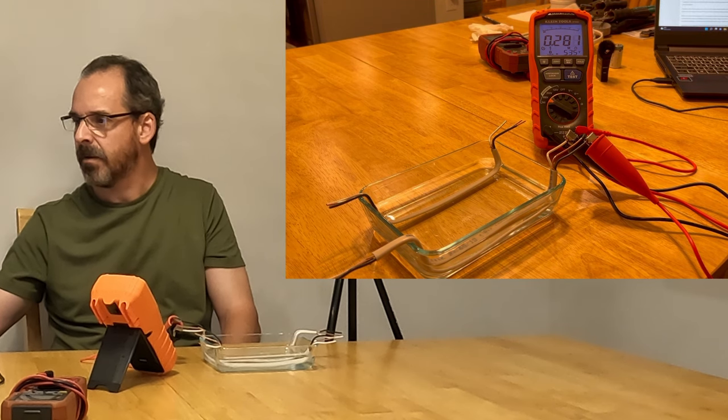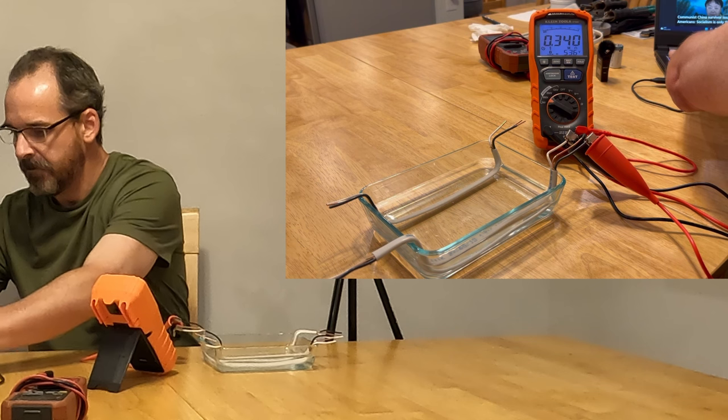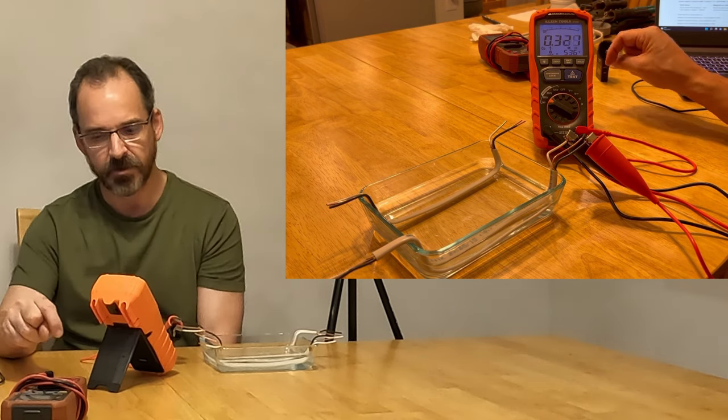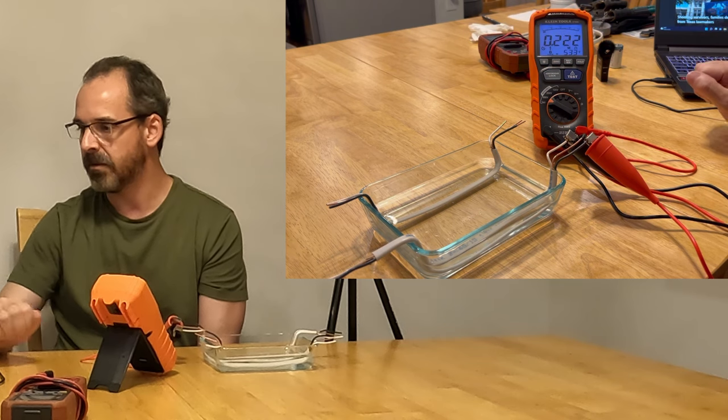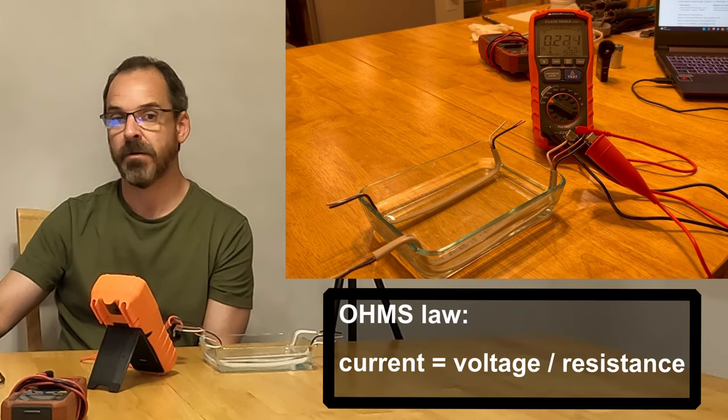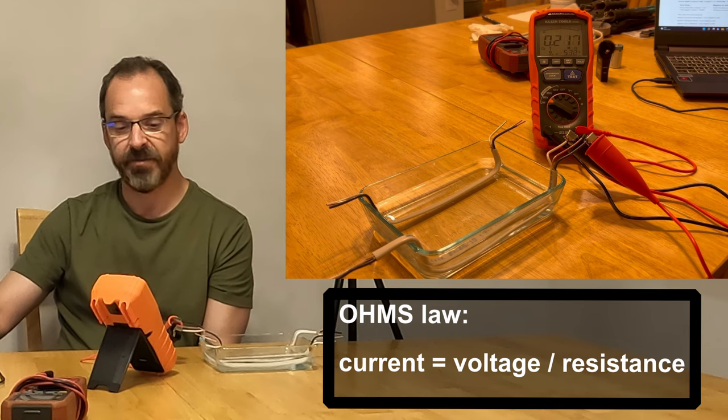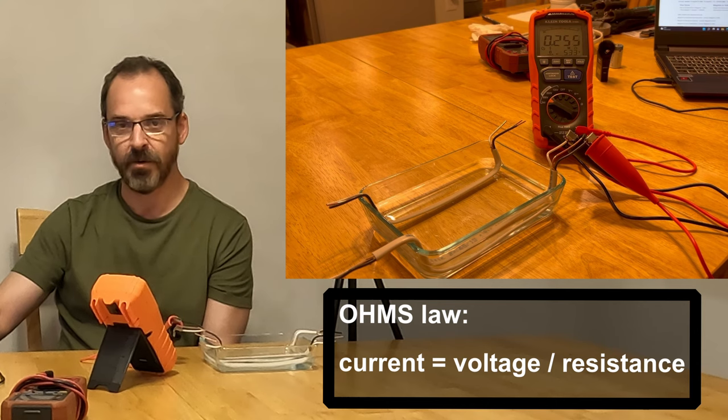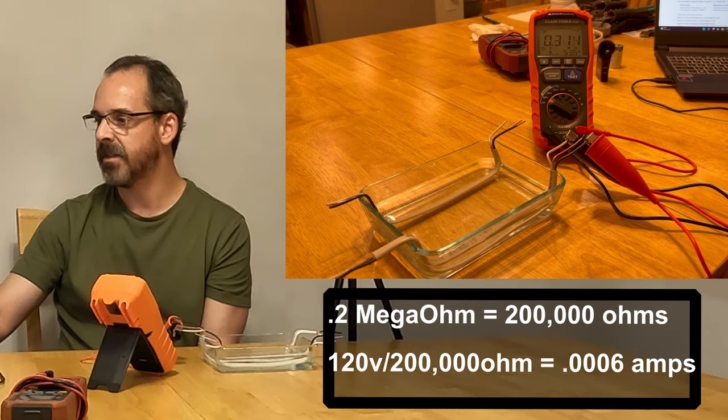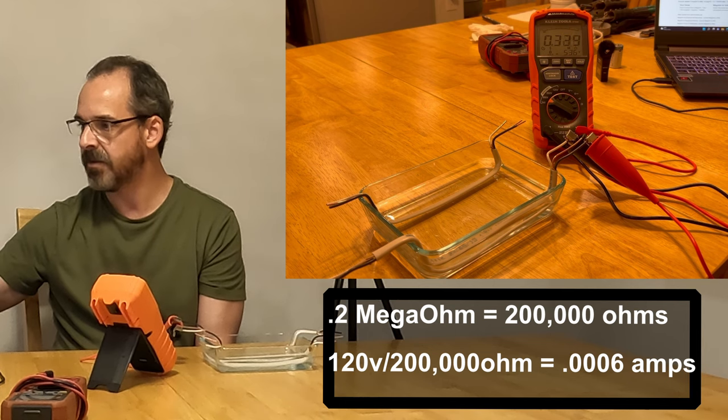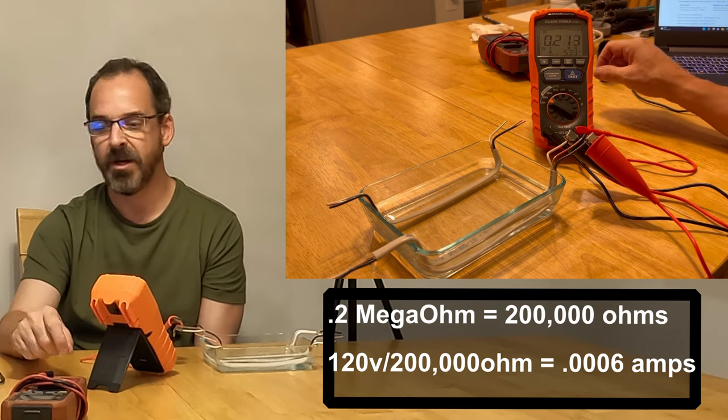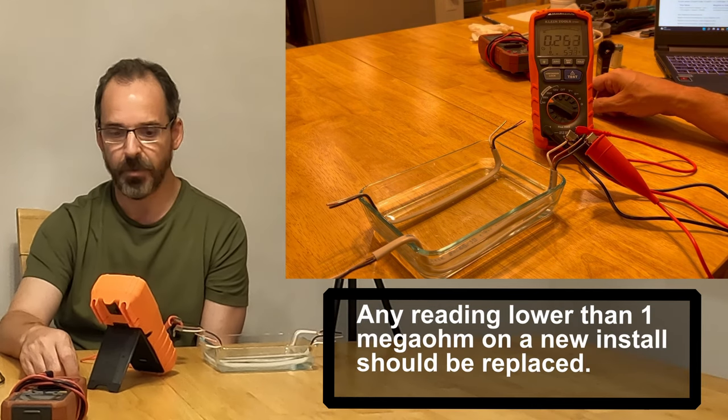Now, let's do a little math. So we have 0.295, still sort of finding itself. We would be using 120 volts on this conductor, so let's see, what does that work out to? So let's do the math on that. Apply Ohm's Law, which is voltage is equal to current times resistance. So what we want to find right now is what would the current be across 200,000 ohms at 120 volts. So what we want to do then is current, which is equal to voltage divided by resistance. So we're going to say 120 divided by 200,000 is 0.0006 amps. That is very, very, very low. It's non-discernable.